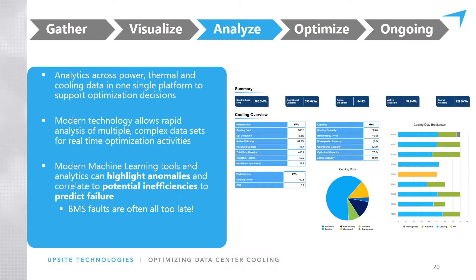Analyzing it and sharing that information in very detailed ways — you can go in and see trends about what's going on. One of the things that stands out is that everybody knows how many tons of cooling they have installed in the data center, but very few people know how much cooling is actually being delivered by each of their cooling units. That kind of analysis can be very easily done and represented in a very clear format.